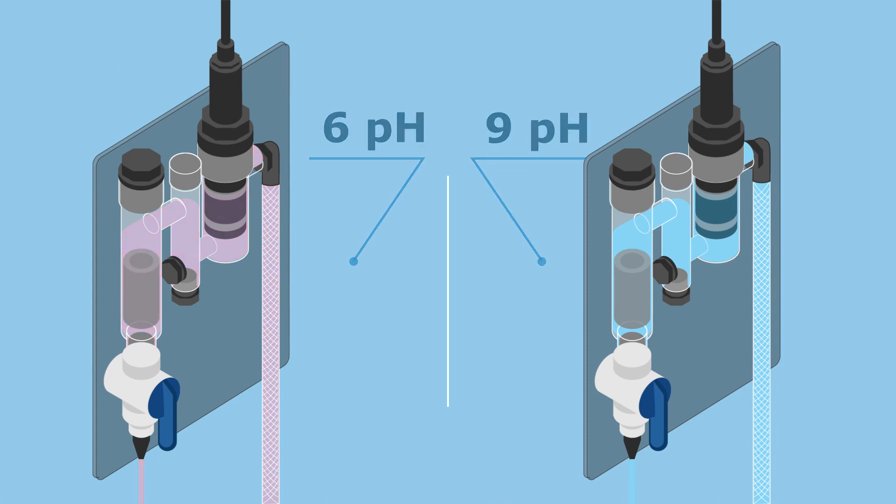This is thanks to an amperometric sensor that is pH independent and provides ranges from 0 to 2 ppm up to 0 to 200 ppm.